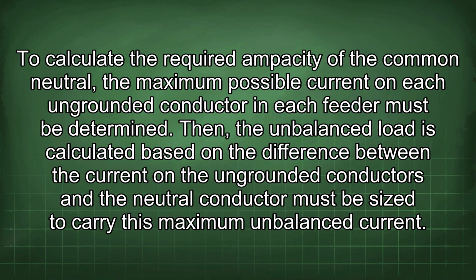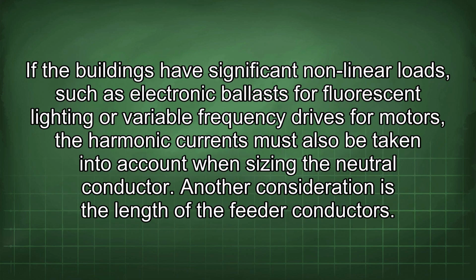To calculate the required ampacity of the common neutral, the maximum possible current on each ungrounded conductor in each feeder must be determined. Then, the unbalanced load is calculated based on the difference between the current on the ungrounded conductors, and the neutral conductor must be sized to carry this maximum unbalanced current. If the buildings have significant nonlinear loads, such as electronic ballasts for fluorescent lighting or variable frequency drives for motors, the harmonic currents must also be taken into account when sizing the neutral conductor.